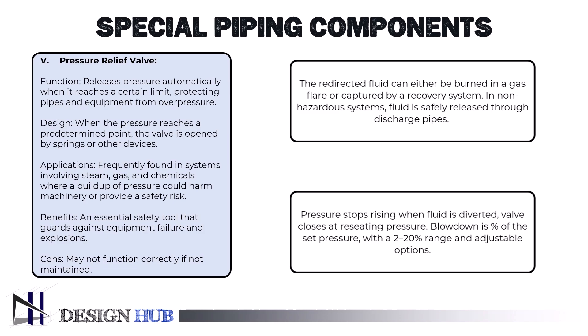The pressure inside the vessel will cease to rise as soon as the fluid is redirected. The valve will close when the pressure inside it reaches the reseating point. The blowdown, which measures the amount of pressure that must drop before the valve reseats, is often expressed as a percentage of the set pressure. There is a 2–20% range in the blowdown, and certain valves have adjustable blowdowns.